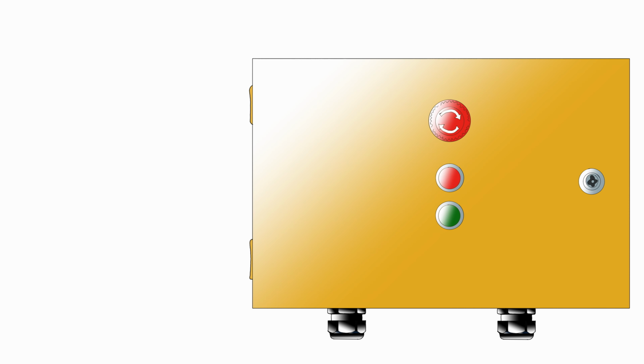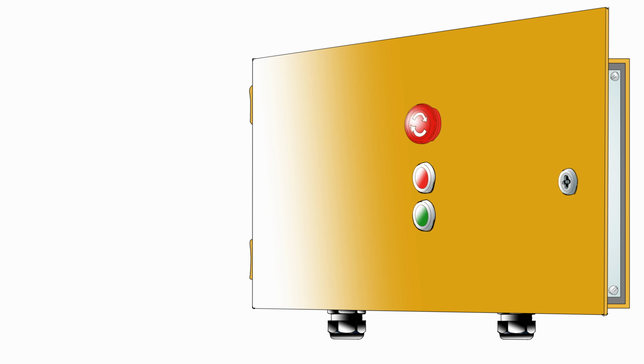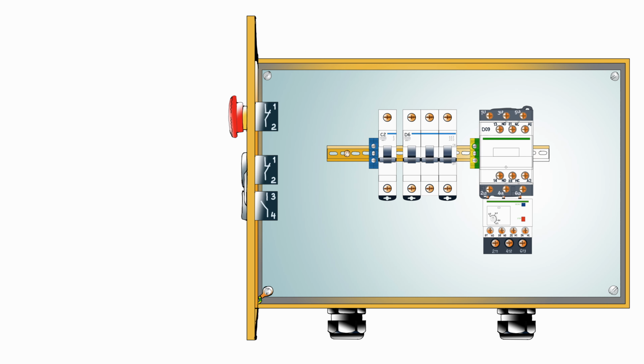Just going to establish that our circuit works before we wire it up. We're going to start with the control circuit. So the first connection is going to the top of the control circuit breaker, and this is coming from one of the phases on our main supply. So we draw from one of the phases to the top of our control circuit breaker, and then we get a connection from the bottom of our control circuit breaker to 95 on our overload relay.